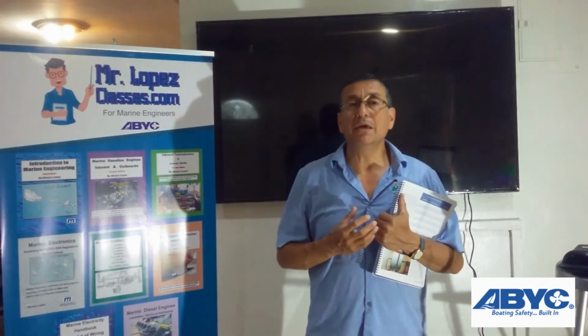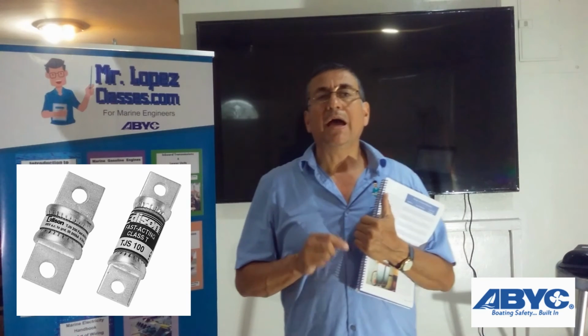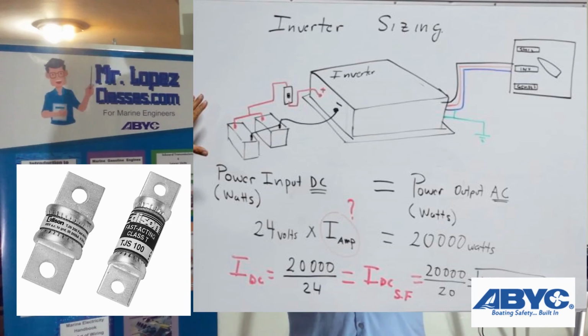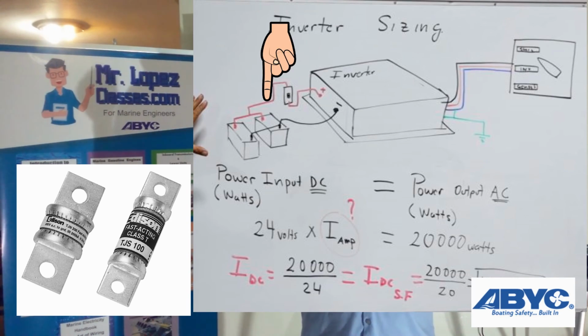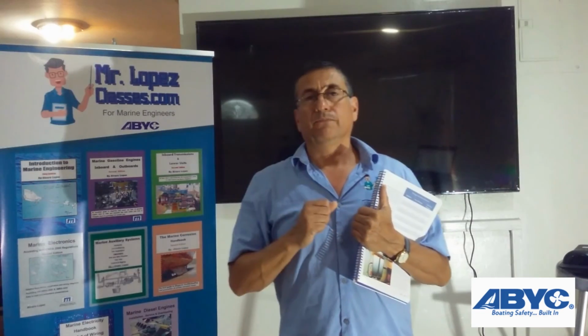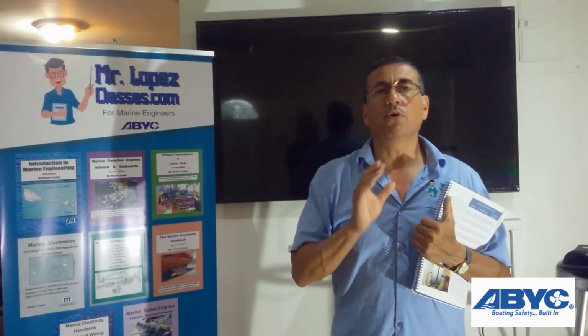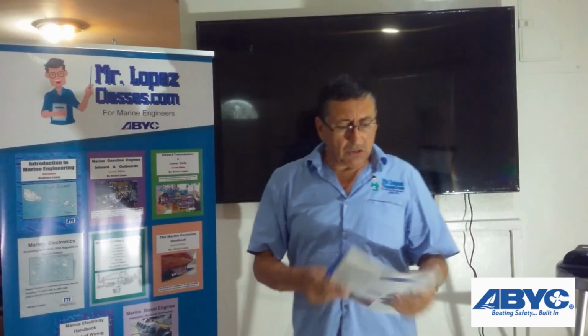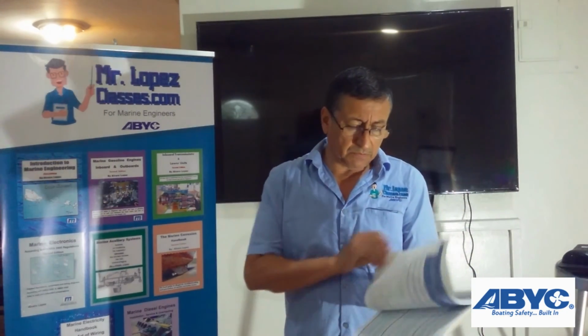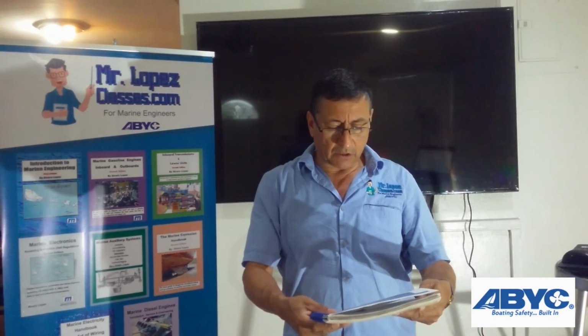And ABYC recommends installing a class T fuse between the battery bank and the main breaker at the input on the DC side, on the DC wire. Between the battery bank and the switch selector or main breaker, you install the fuse in order to protect the inverter. Very, very, very important recommendation. Any other recommendation? No. These are basically the most important recommendations.